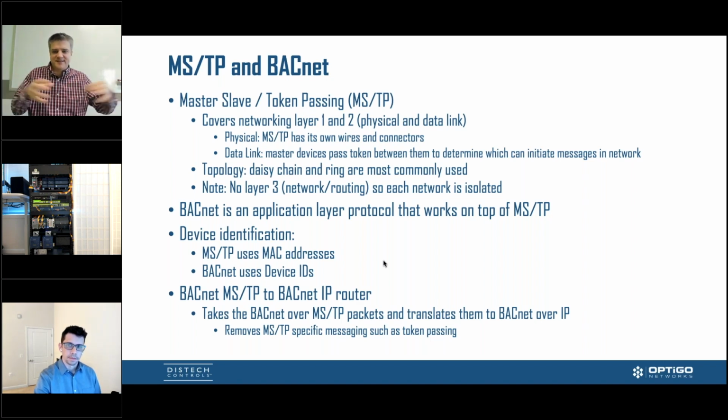All the BACnet traffic that's sitting on top of MSTP is getting taken out of that network and broadcast out into the rest of the network. So it becomes IP traffic at that point. It's a transition point between MSTP and IP, where you can pull BACnet together as a whole in your entire network. I'm not sure if I said that the best way possible, but we'll show you what that means when we show you some live traffic.